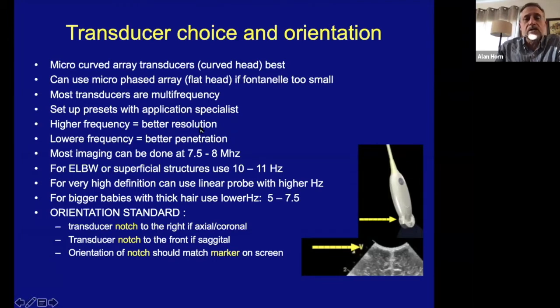So generally a higher frequency is going to give a better resolution, and a lower frequency is going to give you better penetration. In other words, if you use too high a frequency, you won't be able to see deep. You'll see excellent detail higher up, but you won't know what's going on lower down. Now, most imaging can be done at all depths appropriately if you set a middle zone of 7.5 to 8 megahertz. For very small babies, you can probably see the entire brain, even at 10 or 11. And we sometimes will selectively use a very high definition probe when we want to look very superficially. For bigger babies with thick hair, one may need to use a lower frequency or indeed shave the scalp if need be.